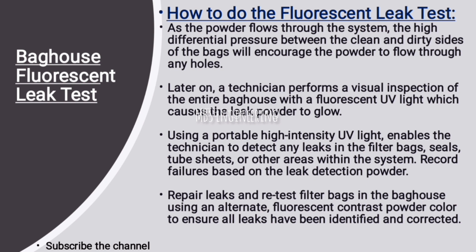Next, repair the identified leaks and retest the filter bags in the bag house using an alternate fluorescent contrast powder color to ensure all leaks have been identified and corrected.